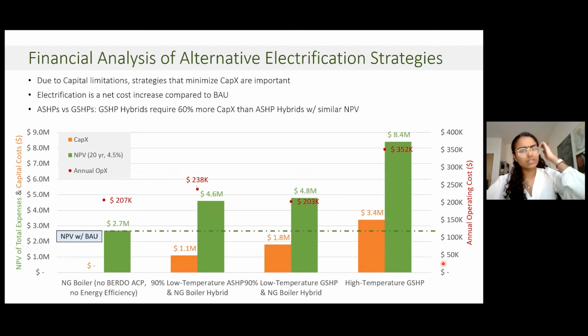And just very quickly, I want to jump into a financial outlay of these different options. What you'll see in the middle is the 2 hybrid solutions that we've discussed: low temperature heat pump and natural gas boiler hybrids. In the orange column, there are capital costs. The red dots show the annual operating cost, and the green columns are the net present value of total expenses. What you'll notice is that the hybrid systems represent a net cost increase from our business as usual case. You can call this our natural gas boiler, the fossil baseline. But what they do represent is a cost cut from what a completely heat pump system would look like.